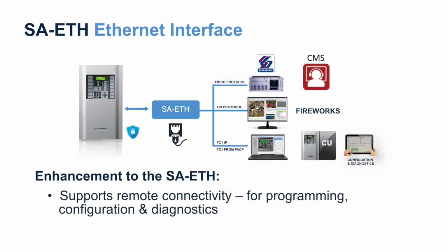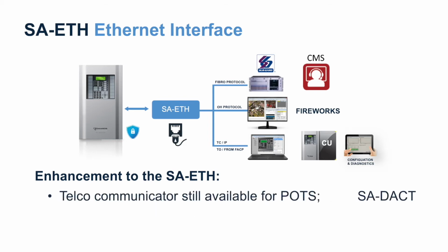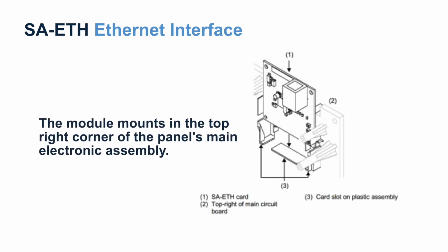Now it supports remote connectivity for programming and configuration and diagnostics, but keep in mind that if any program changes are performed remotely, a technician needs to be on site to perform local testing of any changes made to the system. Our telco communicator is still available for POTS lines, for applications where that method of communication is the only option available at the time. However, by deploying an SA-ETH for IP communications to a central station does help eliminate the costly use of POTS lines. As shown, the module does mount in the top right corner of the panel's main electronic assembly.